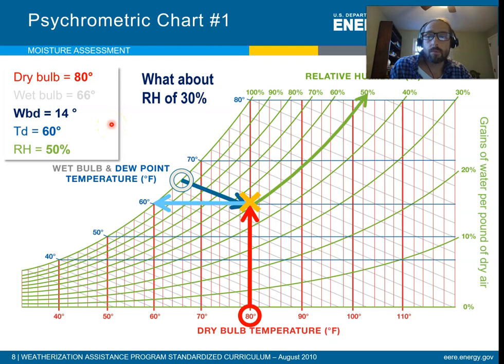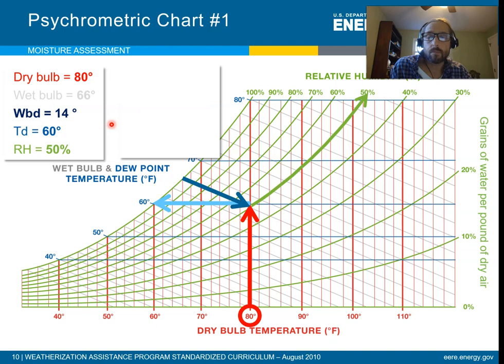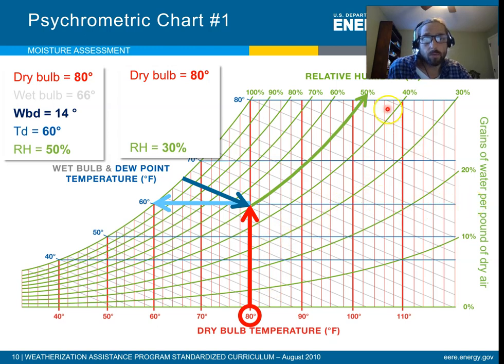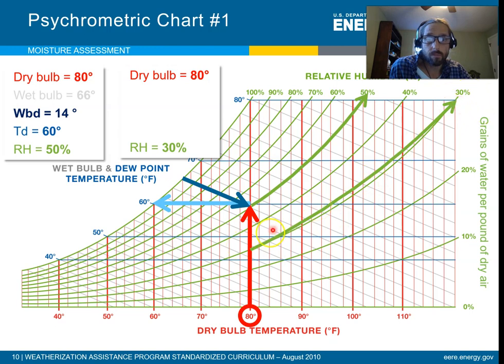What if the relative humidity were 30%? Let's say the dry bulb is still 80 degrees but now we have a relative humidity of 30%. How does that change all the other values? It's just like algebra — if you have two variables, you can figure out the others. You just need any two of these: absolute humidity, relative humidity, dew point, wet bulb, dry bulb. So we find 80 on the dry bulb, follow it up to the 30% relative humidity line. Now see if you can figure out the wet bulb and the dew point.